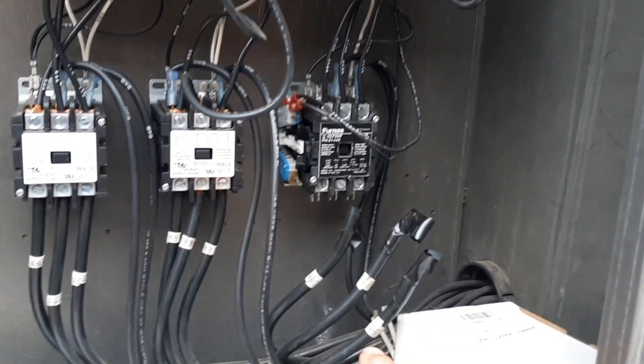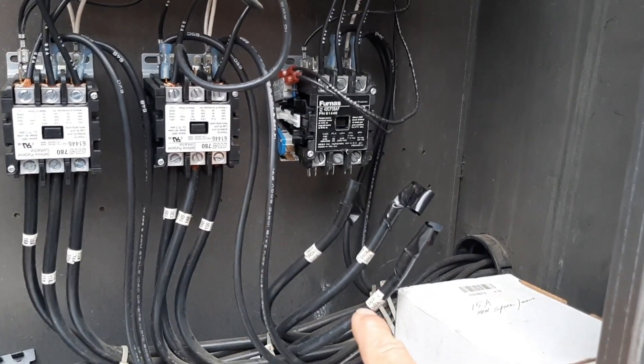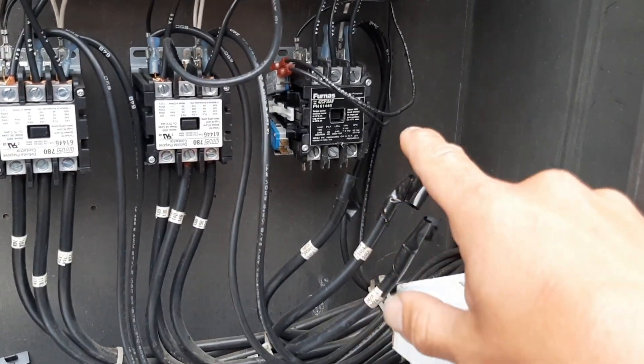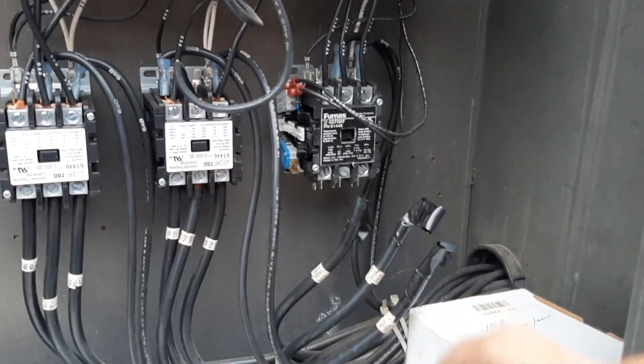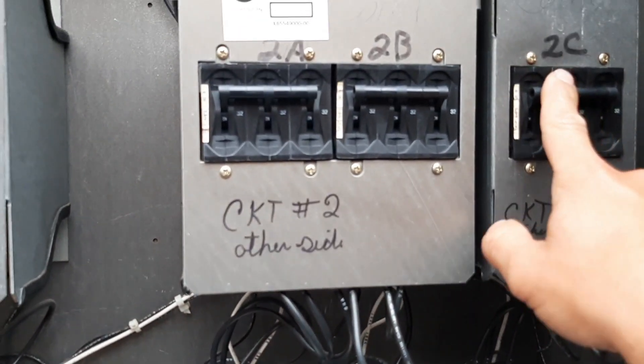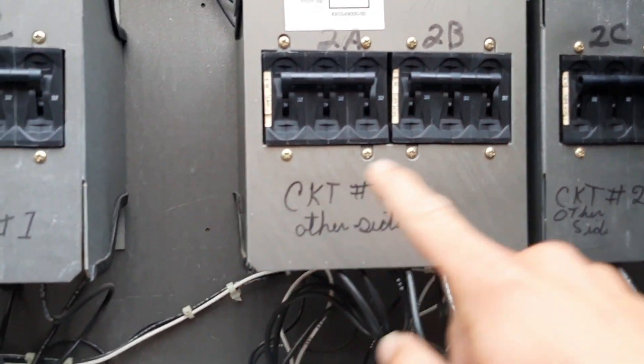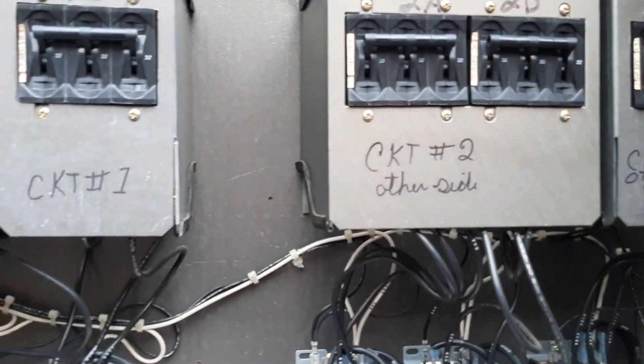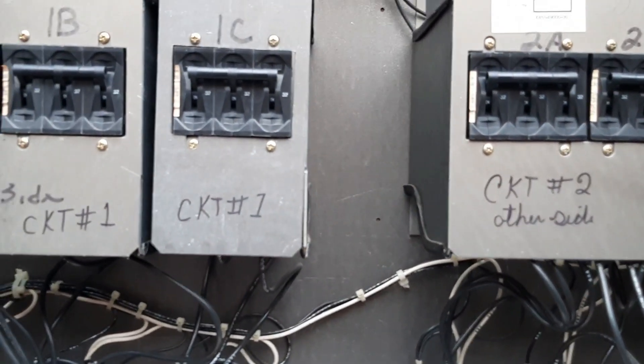This compressor's failed, been failed. That's the only contactor on circuit two that's pulled in. But no overloads are tripped, so I've got power to everything.